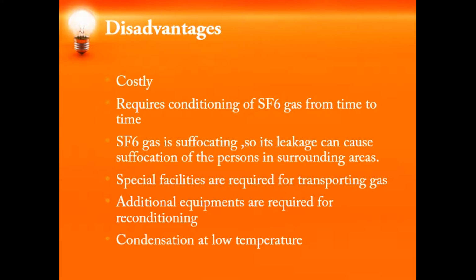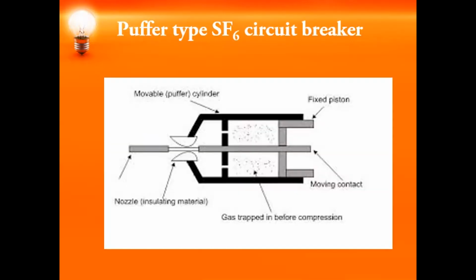Coming to the disadvantages of these circuit breakers, they are costly. Pure SF6 gas is non-toxic, whereas arced SF6 gas is very suffocating and very poisonous, and it should not be inhaled. The SF6 gas needs special facilities for transporting it. You need a special arrangement for transferring the gas and maintaining its quality. The performance and reliability of the SF6 circuit breaker is mainly affected by deterioration of the quality of the gas. You need to maintain the pressure and the temperature as required, else the SF6 will get liquefied.